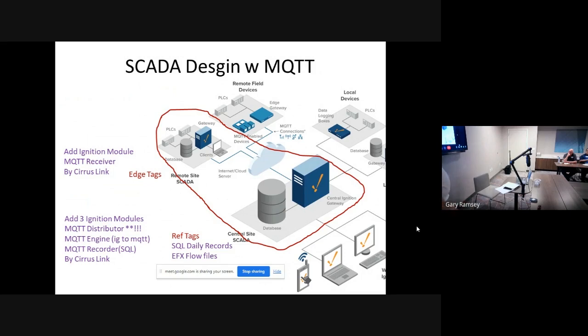It's got tags, what's the pressure, what's the temperature, and these daily records are actually a record, it's a CSV file. That's what it is. It gets created out here in ABB, it gets put on this box. MQTT sees you've got daily records and sends it up to this recorder, and that recorder asks what you want it to do. You want me to put it in the SQL table for this month? Pretty much that straightforward.